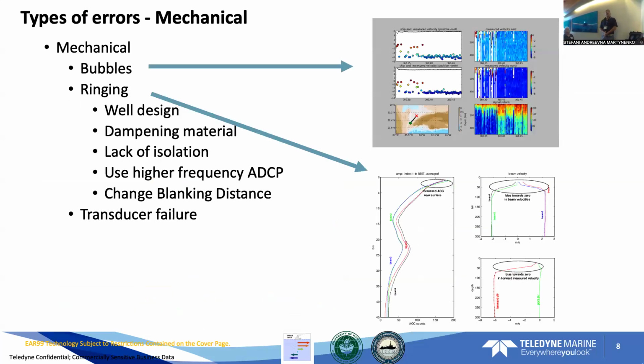The other types of errors we call mechanical. It's bubbles. It's not really, I mean, yeah, mechanical. The bubbles, it's kind of bubble sweep or from storms and things. Nothing we can really do about it. It's kind of like a ship hull design. Then the next one would be ringing, where we have biased beam velocities towards zero, and you're not getting any good velocities. So part of the way to deal with ringing is the well design, put in damping material, lack of isolation, make sure there's bushings, rubber.